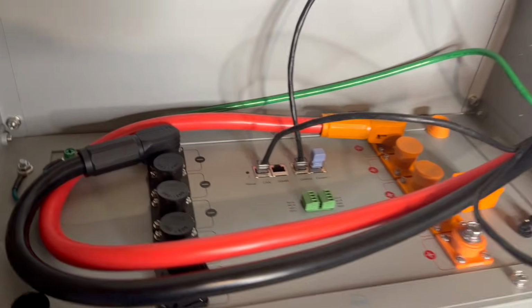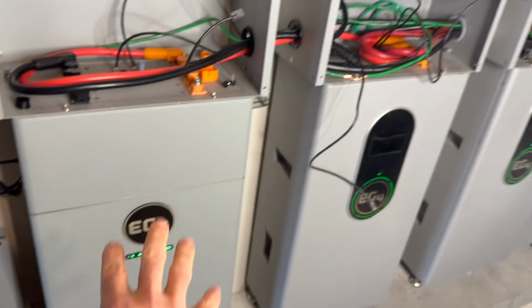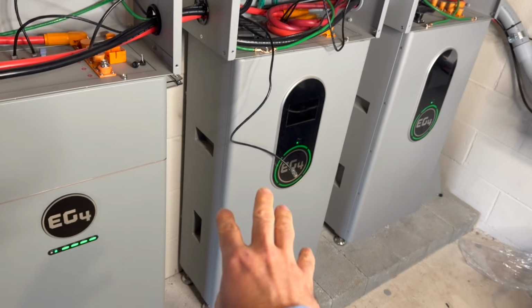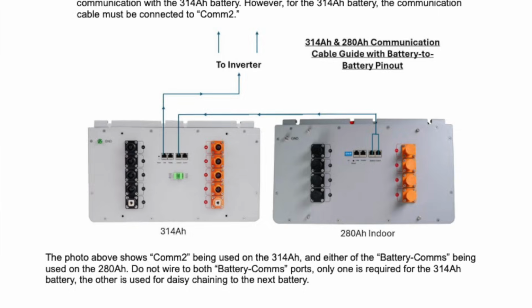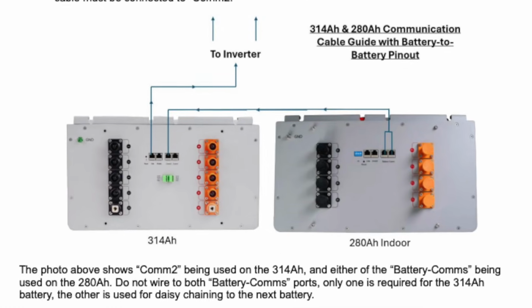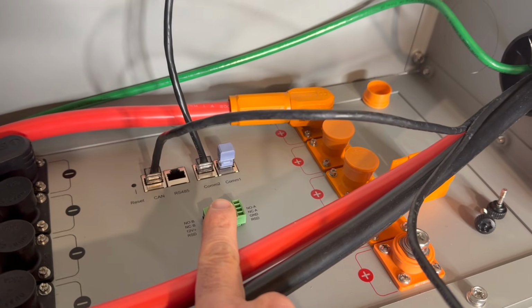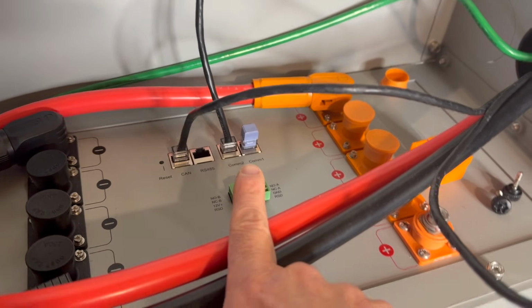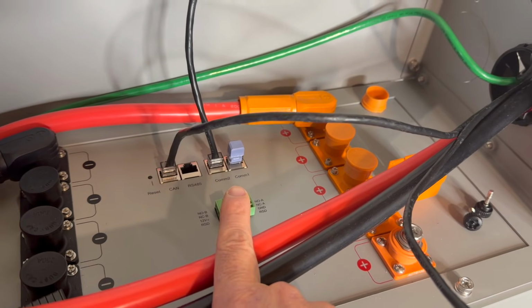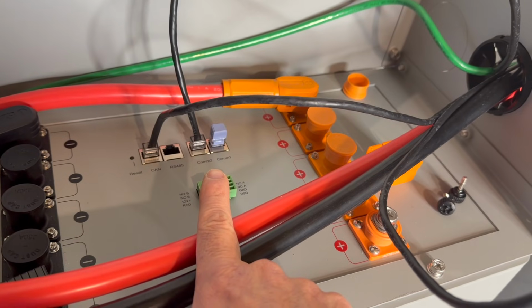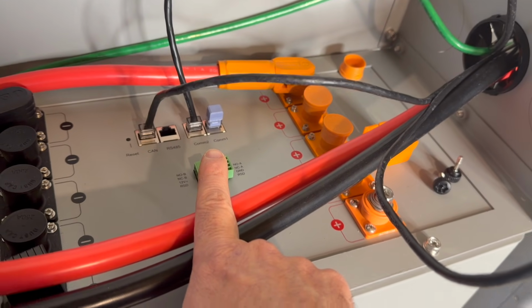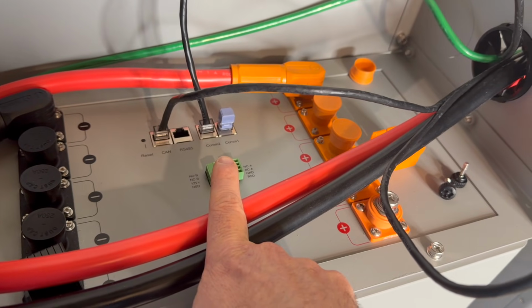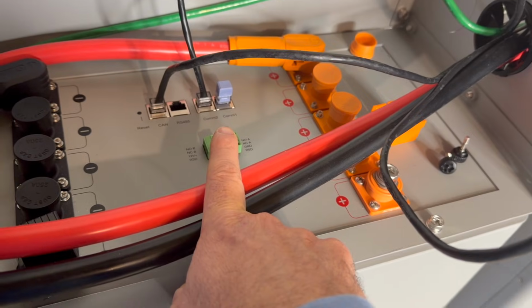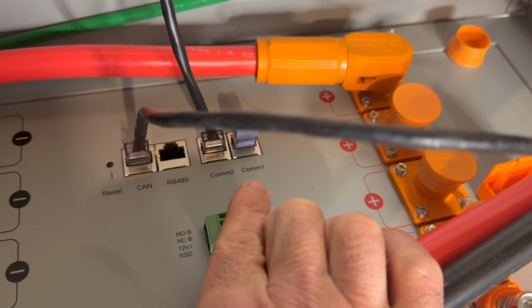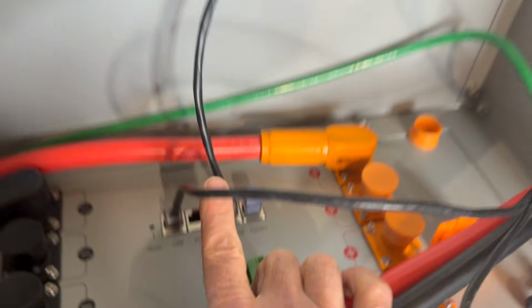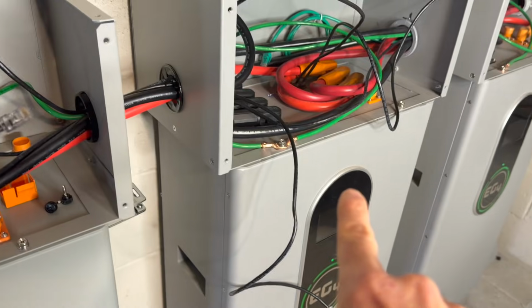So it turns out when you have one single 314 amp hour battery going to 280s, you're going to have these cables and this termination resistor in opposite direction. In my opinion, their paralleling guide, which I'll link in the description, isn't entirely clear on this, because it shows two different illustrations and doesn't clarify which section you use in which scenario. If you have one single 314 and then 280s down the line, you're going to put that termination resistor in COM 1 port, and have COM 2 port feeding from the 314 over to the 280.